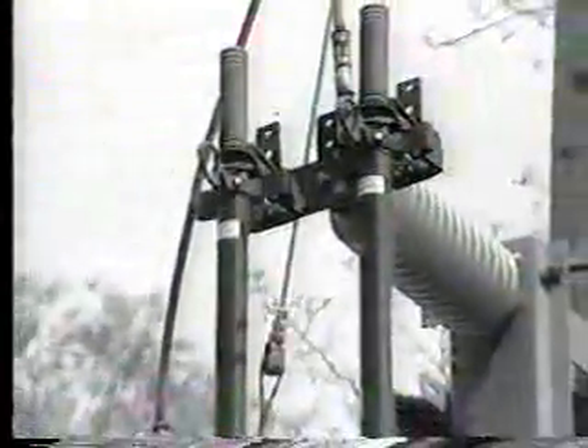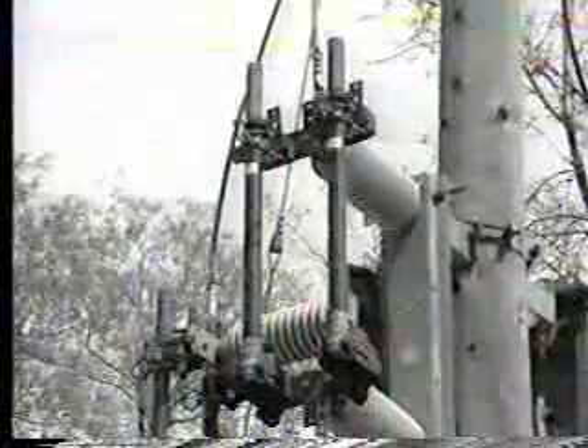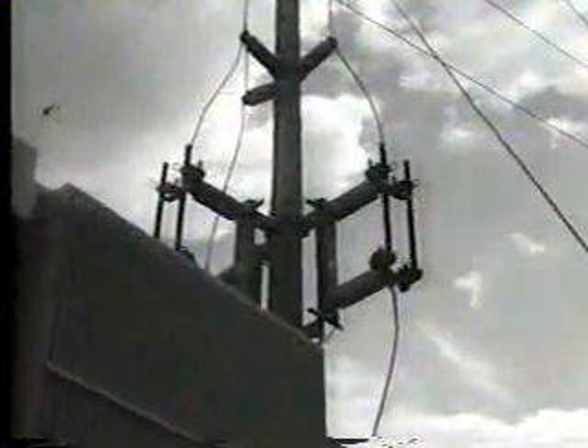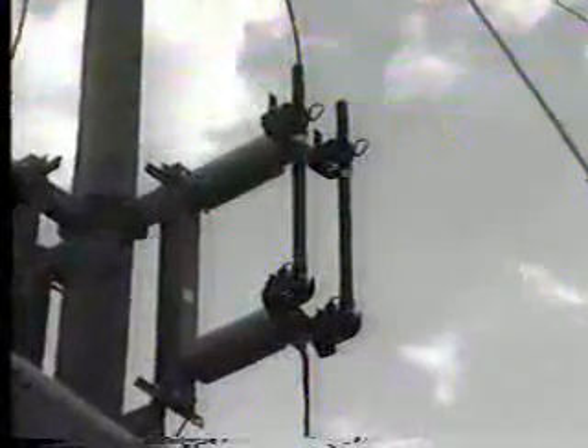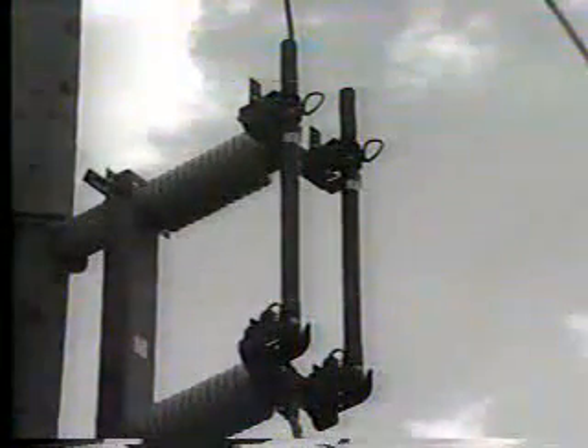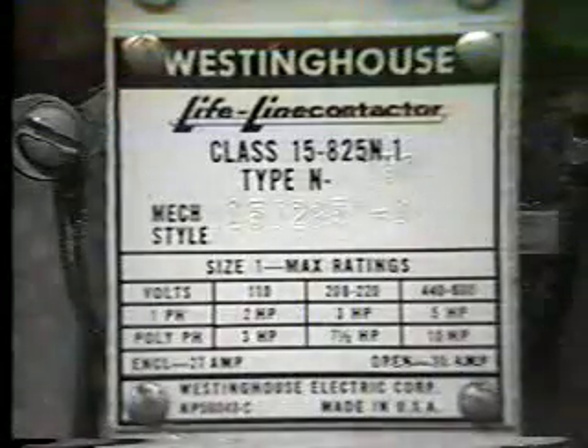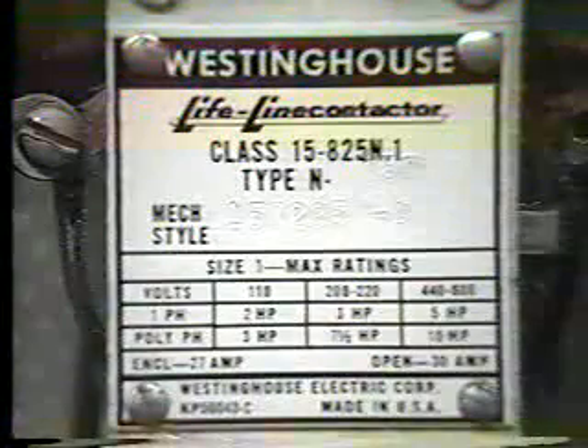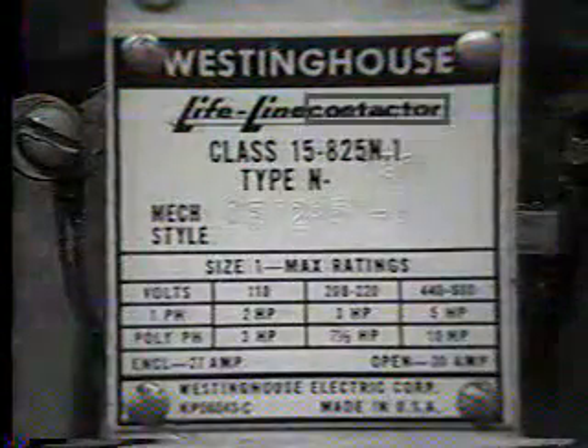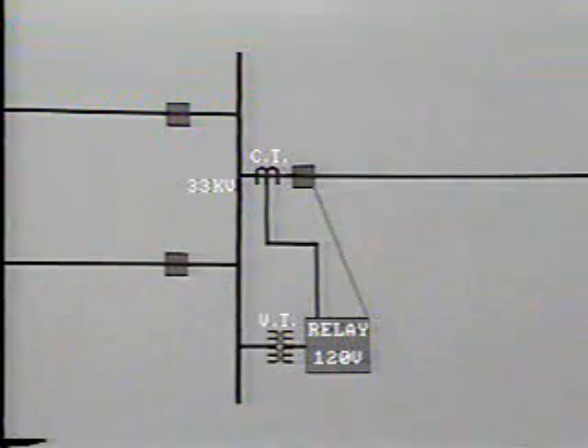On the distribution system, fuses are often used in place of the relay circuit breaker combination. The fuse is not so fast or accurate as protective relays, but it does provide satisfactory economical protection for distribution transformers and feeds. Another type of protection frequently encountered at utilization voltage of, say, 480 volts, is the direct acting contactor. In one common type, overcurrent causes thermal contacts to open the circuit. In another type, a built-in relay opens the contactor. However, let's return to the thrust of this program, that is, protective relaying of the power system.